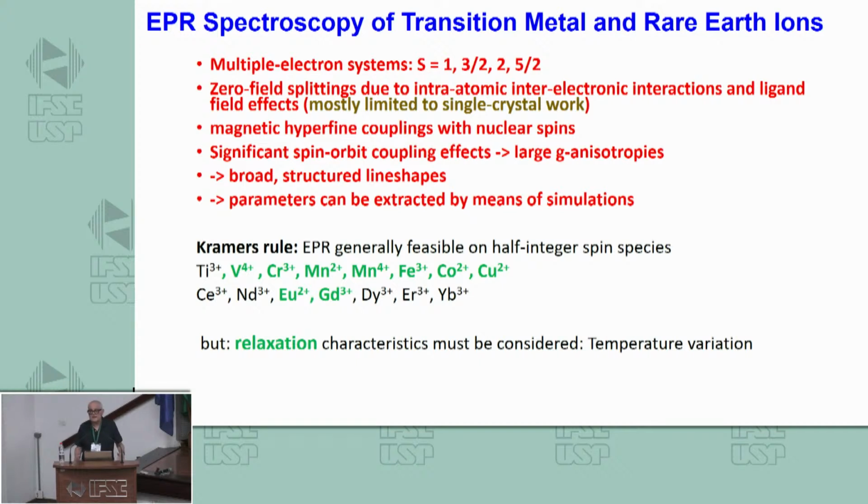And because of Heisenberg broadening, the very short lifetimes of the Zeeman states generate a very large energy uncertainty. You cannot observe an EPR signal of many titanium 3 plus species at room temperature. What you have available is temperature. So you go to liquid helium, or maybe sometimes liquid nitrogen is sufficient, and then all of a sudden you get a signal.